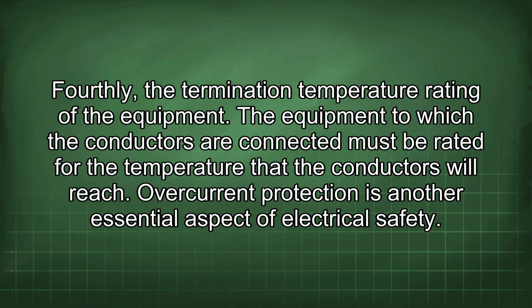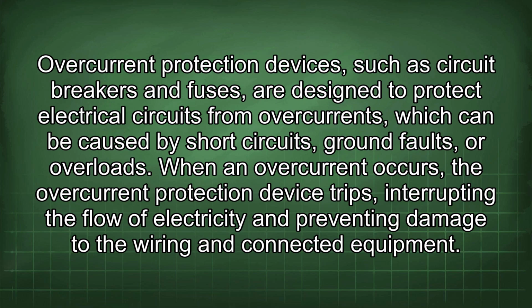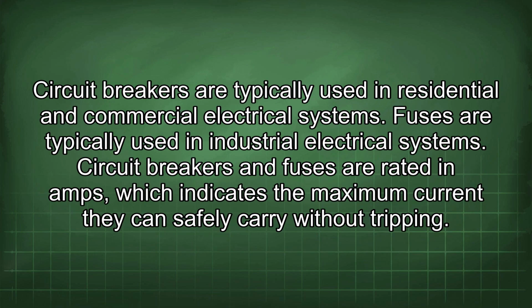Overcurrent protection is another essential aspect of electrical safety. Overcurrent protection devices, such as circuit breakers and fuses, are designed to protect electrical circuits from overcurrents, which can be caused by short circuits, ground faults, or overloads. When an overcurrent occurs, the overcurrent protection device trips, interrupting the flow of electricity and preventing damage to the wiring and connected equipment. Circuit breakers are typically used in residential and commercial electrical systems. Fuses are typically used in industrial electrical systems.